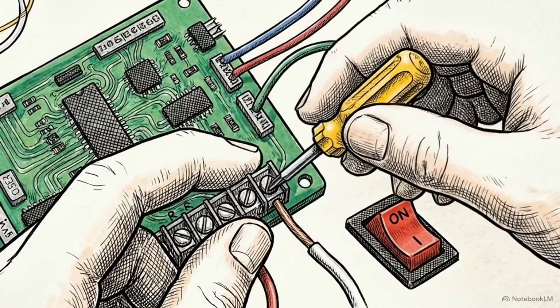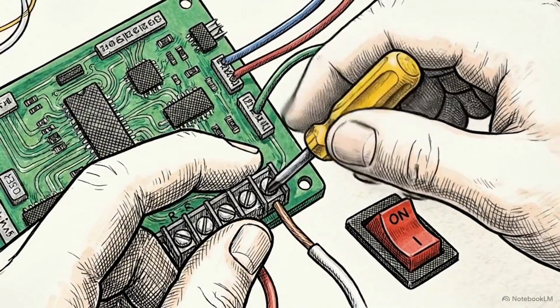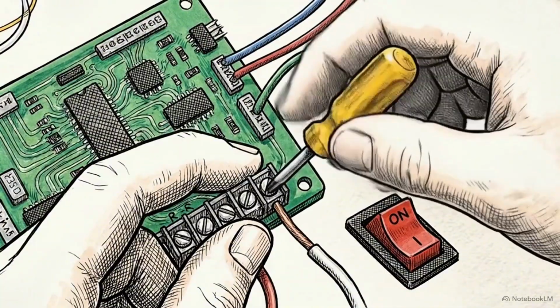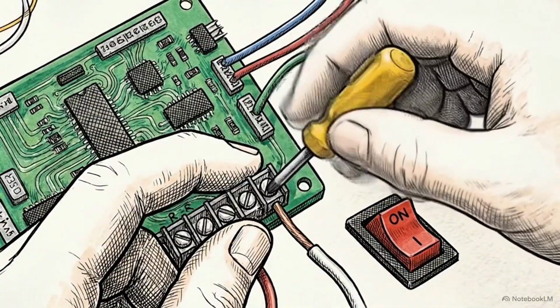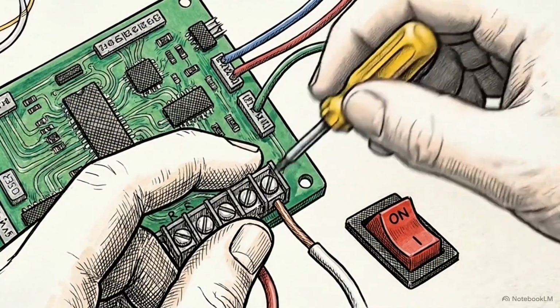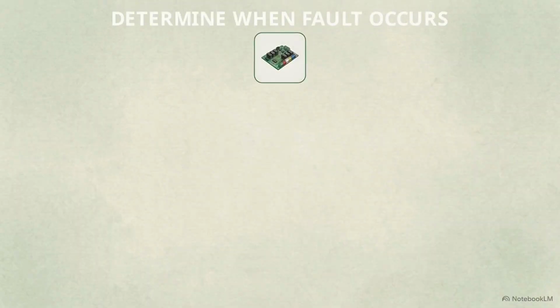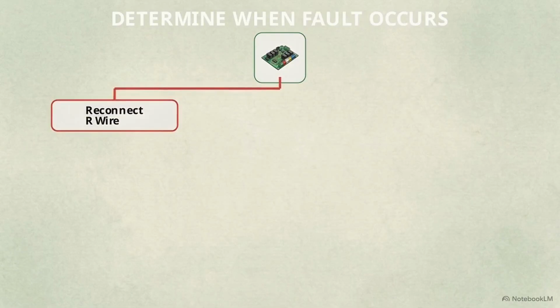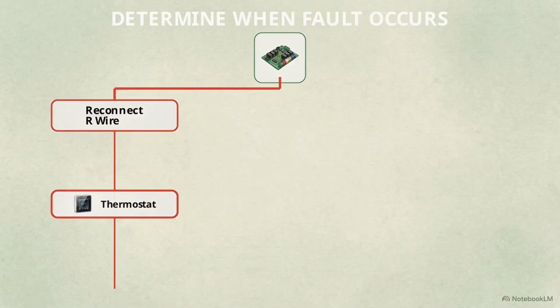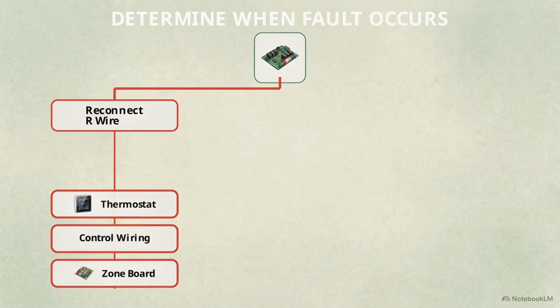Now, we systematically reconnect the field wiring, one branch at a time. Always turn the power off before reconnecting a wire, then restore power to test it. This diagnostic flowchart maps the process. Step 1. Reconnect the R wire and restore power. If the breaker trips immediately upon connecting R, the fault is highly localized to the thermostat, the control wiring, or a zone board. If the breaker holds steady with R connected, initiate a specific operating call.